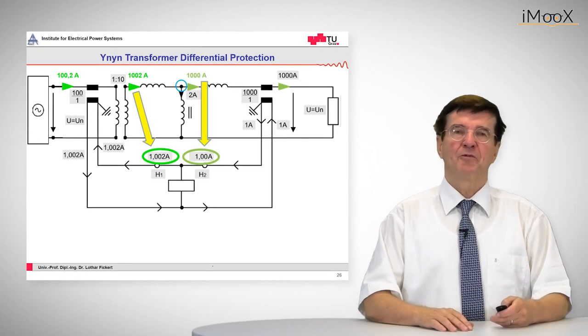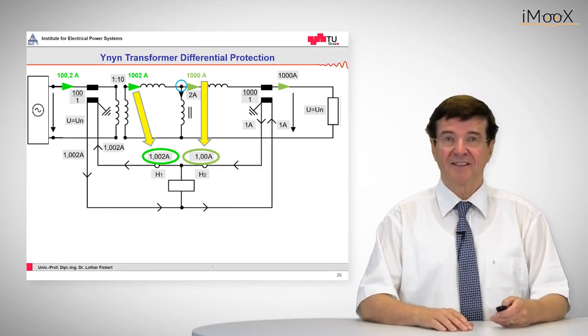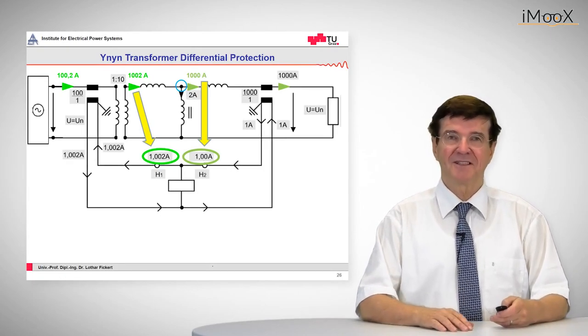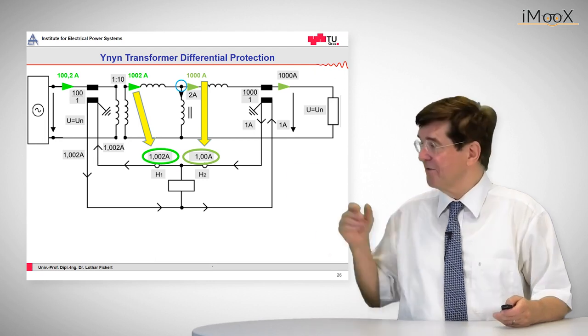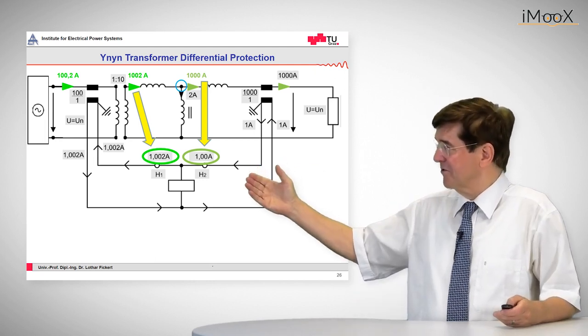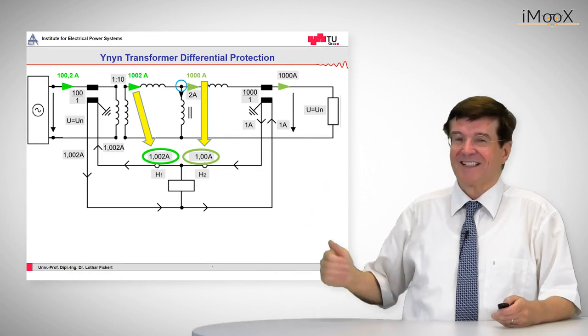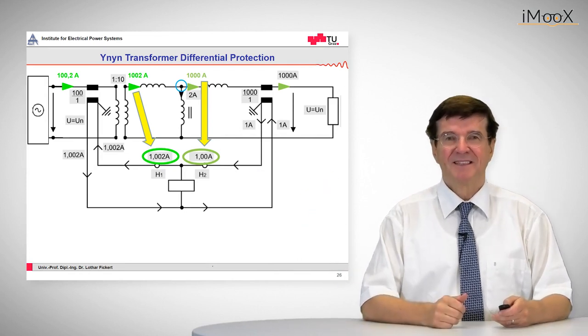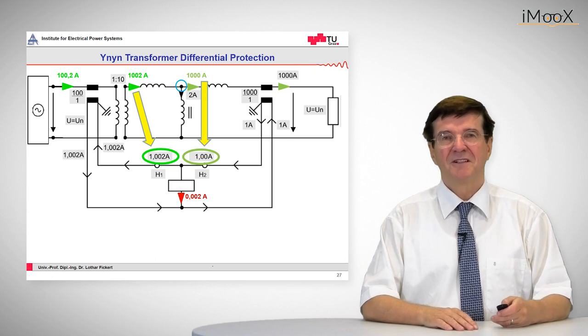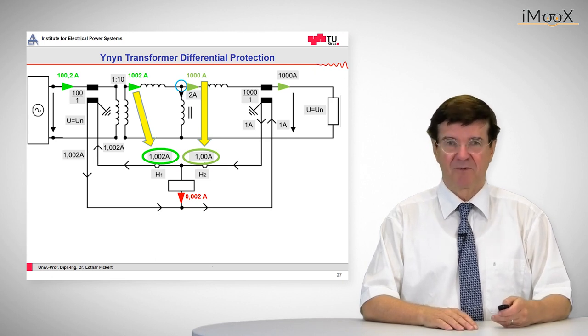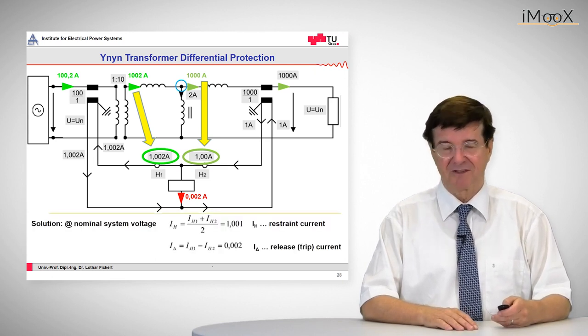And that means if we see what is the effect on the secondary side of these current transformers, we see that we have on the left side 1.002 amps and on the right side 1.00 amps. So the difference is 0.002 amps, which is very small but it is a differential current.